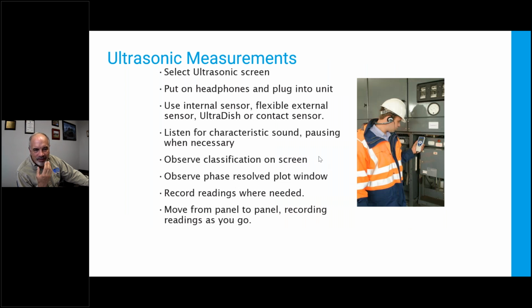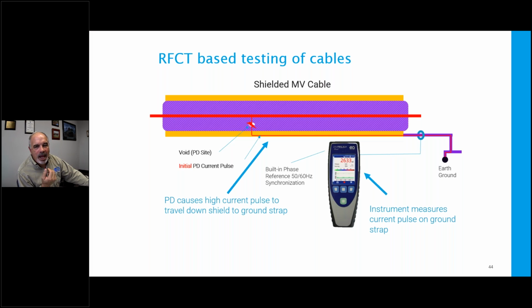Ultrasonic measurements, I think I've beaten this one to death, but basically you're wearing the headphones, you're listening, you're looking through air gaps, and you're watching the screen. Cable PD measurements, the challenge with PD cable measurements is you've got to get the RFCT or HFCT on the cable, right? Those cable terminations are not always visible. In Europe, IEC style switchgear has the cable grounds outside the cabinet. US style switchgear has cable grounds inside the cabinet. Riser poles, obviously, you can get to, and ground straps on transformers and things like that you can get to, but the individual cable terminations can be difficult.